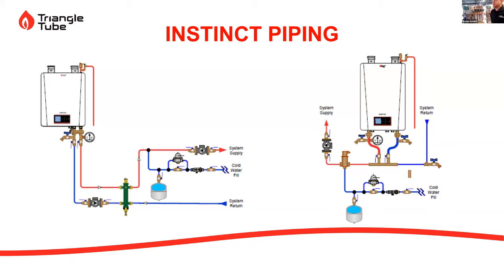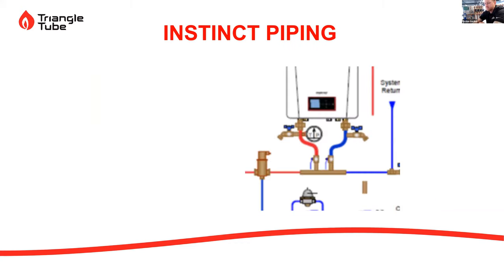Still, with a lot of those applications, I like to see closely spaced tees or low loss headers. But with the pricing on low loss headers now, and time and labor, this thing just makes sense. It's all this right here wrapped up into one nice tight unit, so it makes it a little bit cleaner. It works really well. When guys use low loss headers, I get zero calls on delta T's and pumping issues. Closely spaced tees, if not sized and installed properly, I'll get calls on delta T and have to go out, take a look, and we'll end up having to change piping or pumps. So if you use low loss headers, great. If you're using closely spaced tees, just make sure you're doing it correctly.